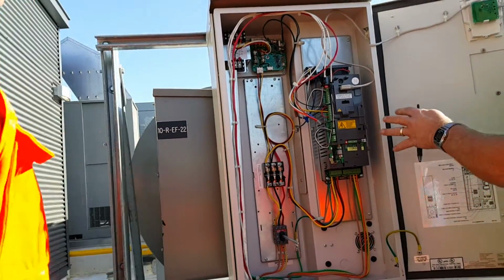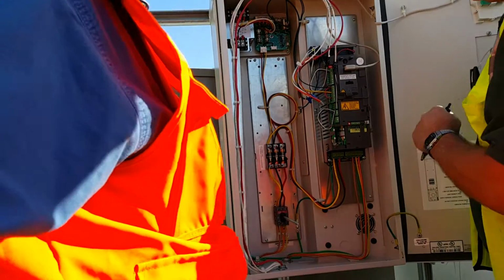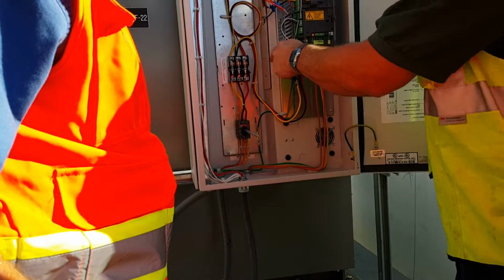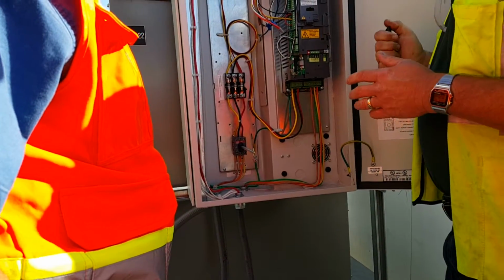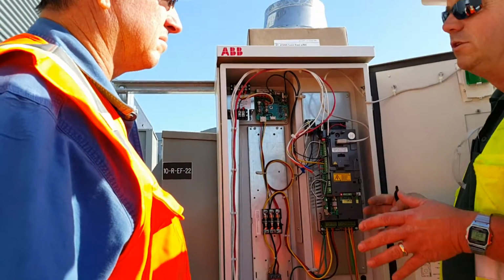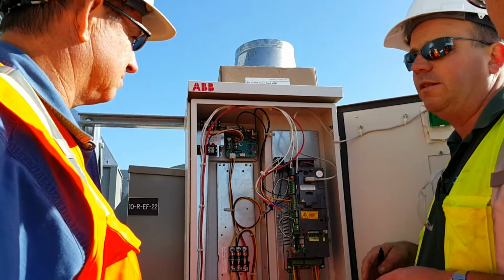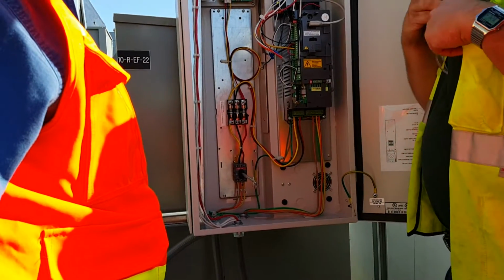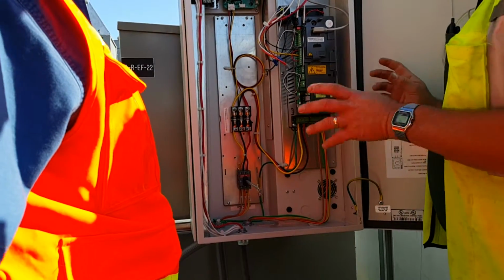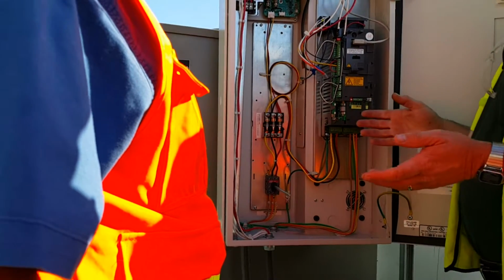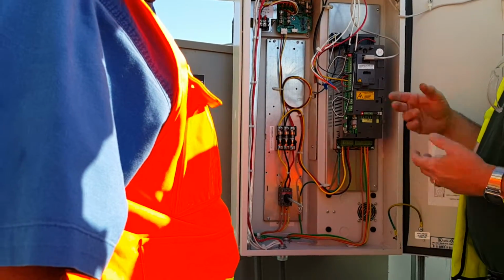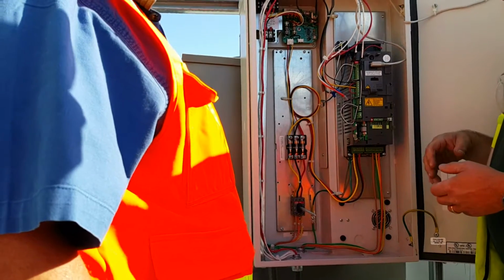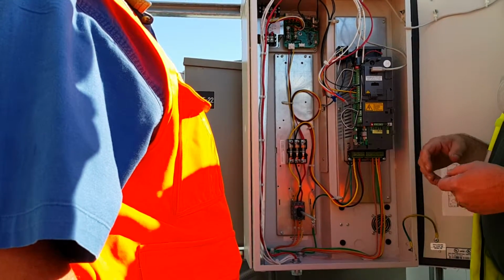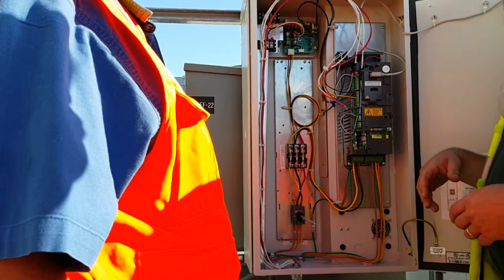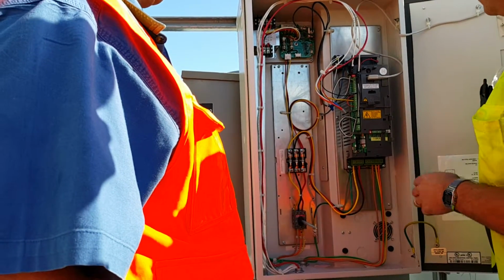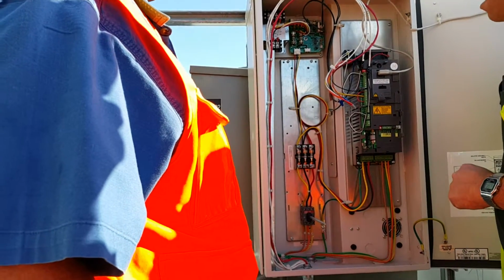Here's the inside. So this is the drive itself right here. Okay. So our power comes in, or disconnect. We've got fuses there. If you come up to the drive and all 3 fuses are blown, don't just replace the fuse. There's something currently shorted. There's something bad. Like I tell people, 2 serious events may happen. You replace the fuse, nothing happens. It's not going to come back up again because whatever short is blown open is now the fuse, right? The other thing is the big pop sound is going to happen that you missed earlier. And it's always nice to miss those. There's something usually seriously wrong.